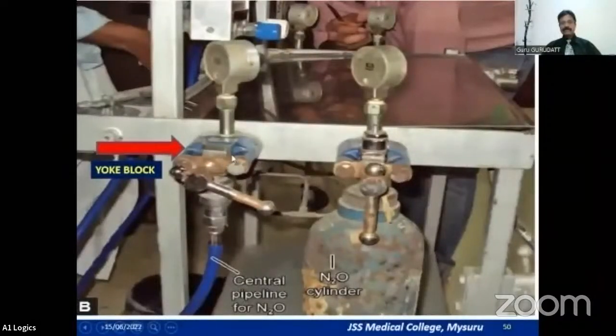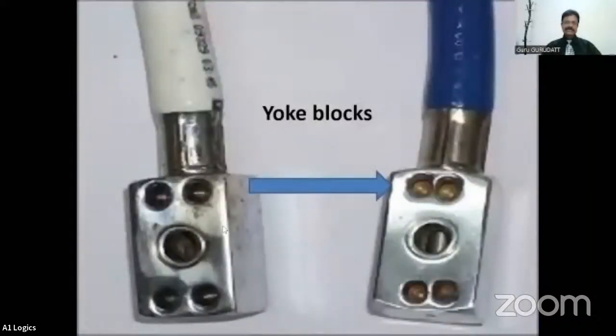I told you that these yoke blocks resemble the cylinder valves. So sometimes you'll be asked, especially, what is this particular thing that is present at the end of the central pipelines for the older machines. They are called the yoke blocks. You can see these are the yoke blocks. You can see here the yoke blocks also have the pin index holes, so that you cannot connect a nitrous oxide pipeline onto the oxygen yoke and vice versa. That's the safety feature that is adopted there.